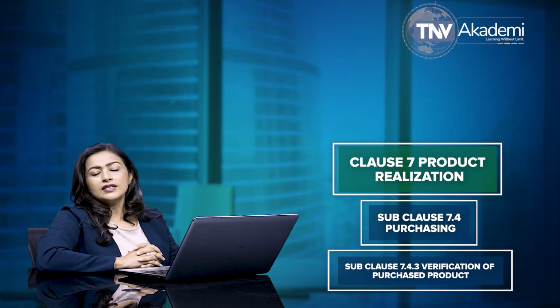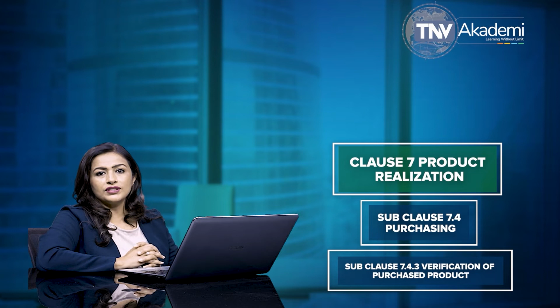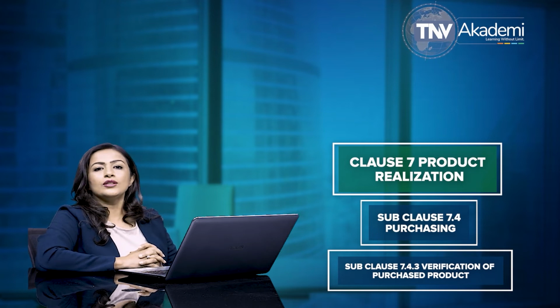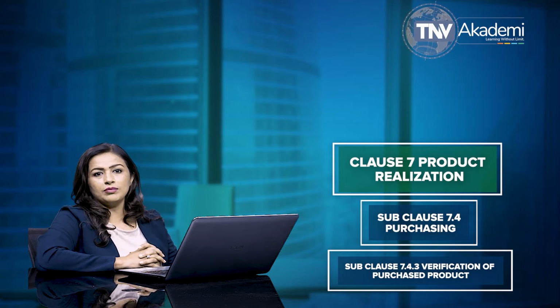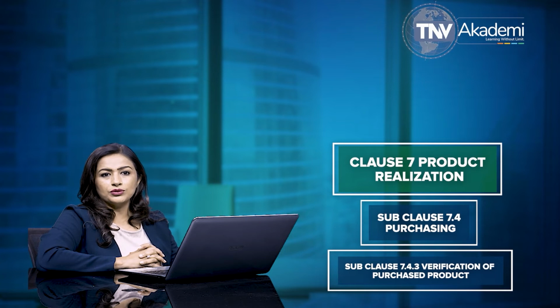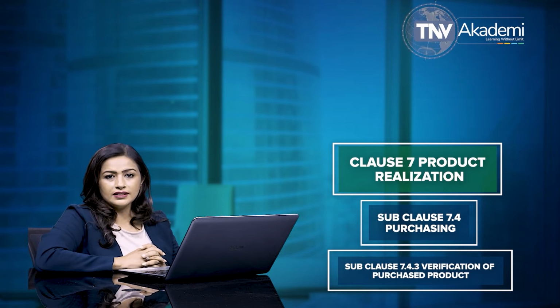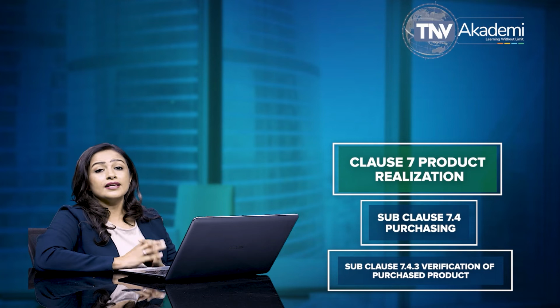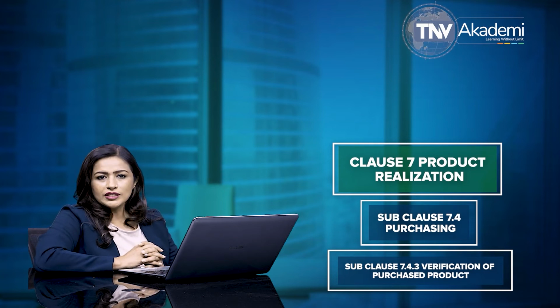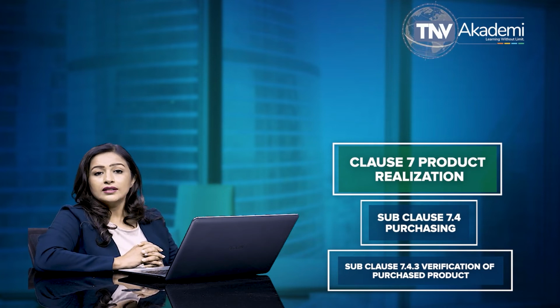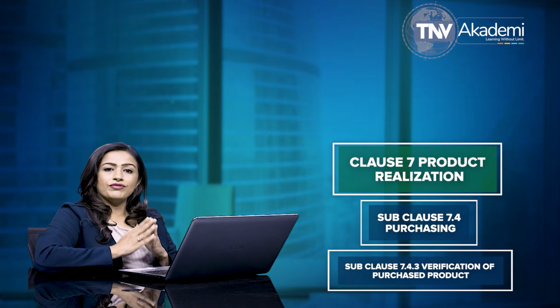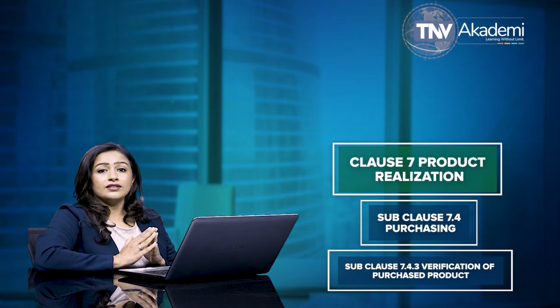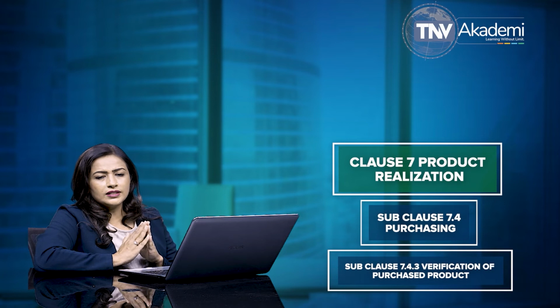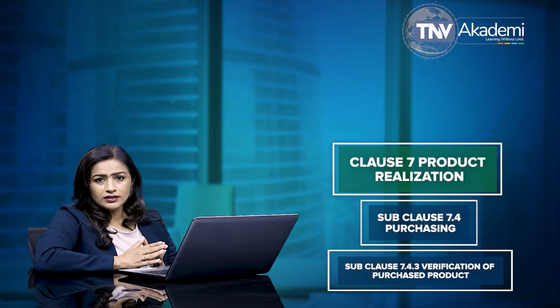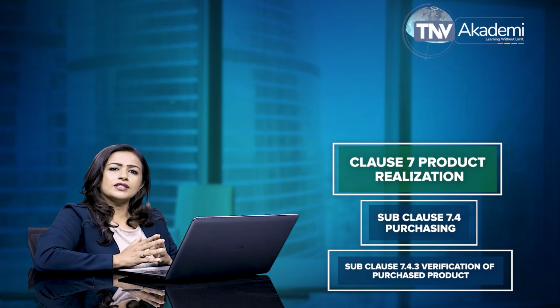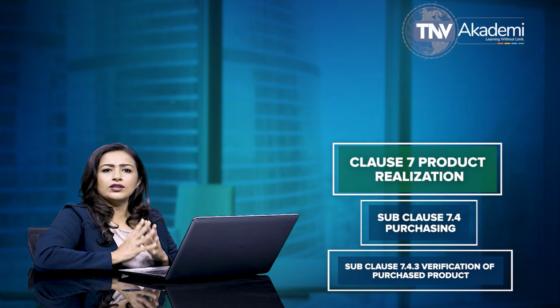This subclause 7.4.3 of the standard specifies that the organization is required to establish and implement the inspection or other activities necessary for ensuring that purchased product meets specified purchasing requirements. This clause says that the extent of verification activities is required to be based on the supplier's evaluation results and proportionate to the risks associated with the purchased product.